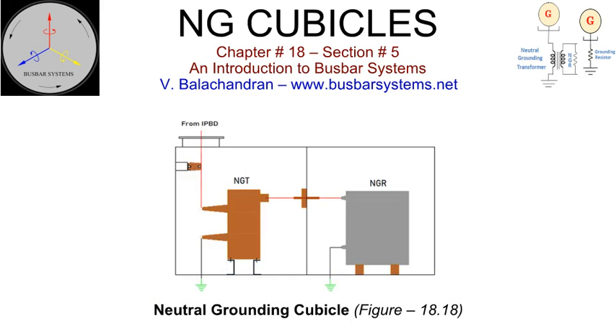Neutral grounding cubicle. The neutral grounding cubicle houses a neutral grounding resistor in case of low impedance grounding, or a neutral grounding transformer and a neutral grounding resistor in case of high impedance grounding. The primary of the neutral grounding transformer is connected to the generator neutral after star formation, either through a single-phase metal enclosed bus terminating on a flange on top of the cubicle or a cable terminating in a cable end box on the side of the cubicle. The neutral grounding transformer and the resistor are installed in separate compartments with wall-through bushing for connections. Depending upon the project requirements, the neutral grounding cubicle may also contain an isolator, medium voltage current transformer and voltage transformer for input to protection relays.